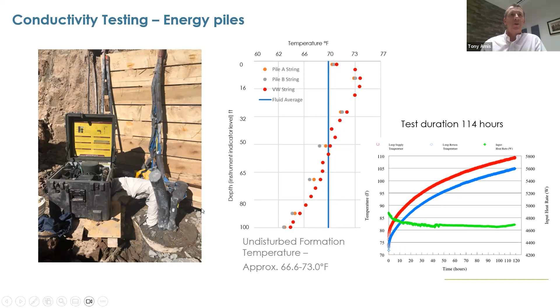Again, we get a lot of conductivity values, so we can confirm the design. What's important is long-term monitoring. With any geothermal system, it's important that you don't just walk away once it's installed. We want to provide long-term management and monitoring, because, as I just alluded to, we can start to play around with the ground temperature, so that come the summertime, we've got nice cool ground, such that we can deliver a whole lot more cooling than we originally said. Then we can put more heat into the ground, and in the wintertime we can deliver a lot more heating in a much more energy efficient way. We would call that system optimization.